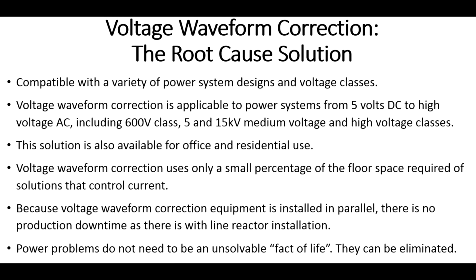This process of correcting the voltage waveform works in virtually any power system, from 5-volt DC through 600-volt class equipment, residential, office, high voltage, medium voltage, power grid level. It's all directly scalable. It actually takes a very small percentage of the floor space that would be required if you're trying to clean up power by controlling, or attempting to control, current.